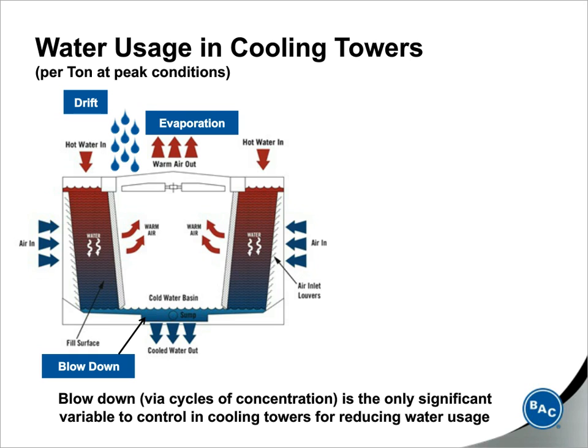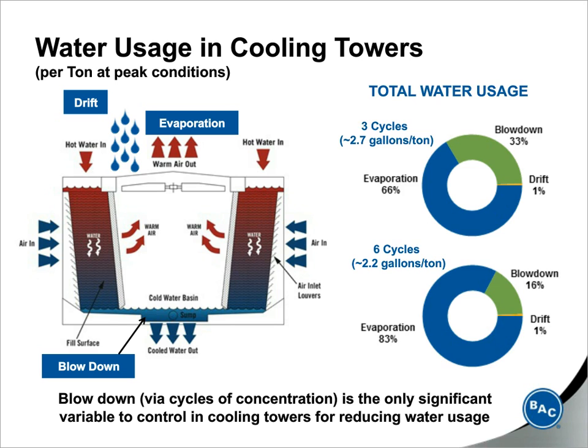across all towers. Now, blowdown, on the other hand, can be controlled. And blowdown is the discharge of water from the system that maintains the desired water quality level. So by using more advanced materials of construction, like the polyurethane coating, there's a great opportunity to reduce on-site water usage.